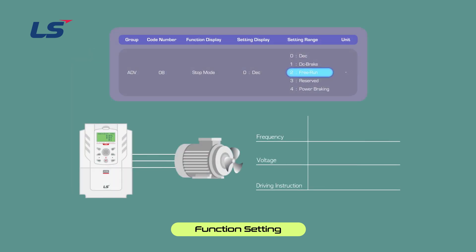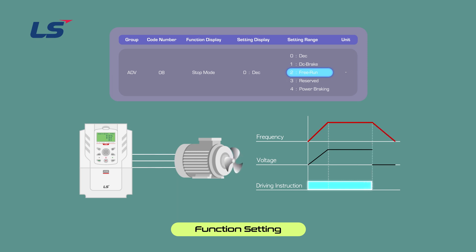Free Run stop method is a function that blocks the AC drive output when the operation command is turned off. Even when the AC drive output is blocked, if the load inertia of the motor is large and operating at high speed, the motor may rotate due to inertia for a long time. The Free Run stop method has the same effect as equipment that operates on direct line. When Free Run stop is used, regenerative energy from the motor is blocked from entering the AC drive, and an overvoltage trip does not occur.